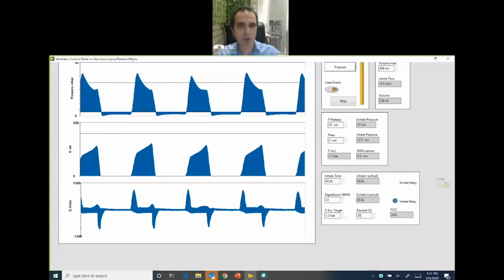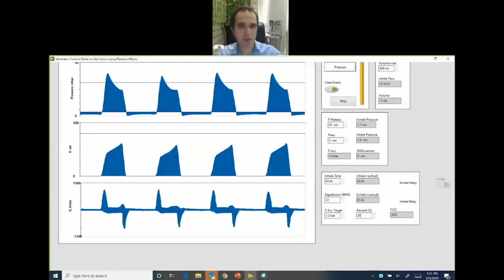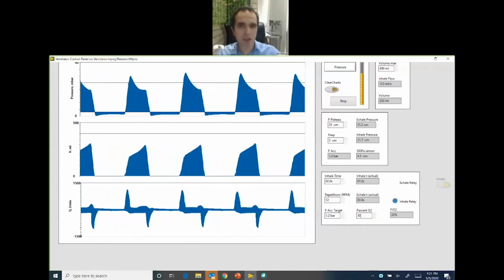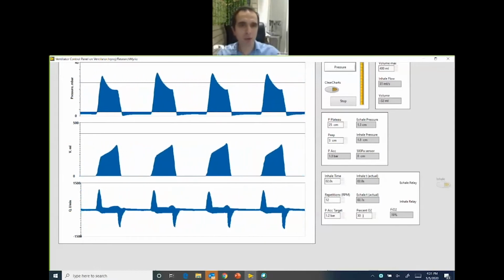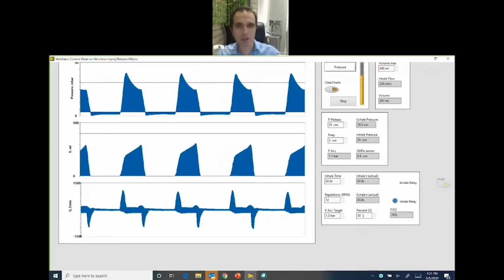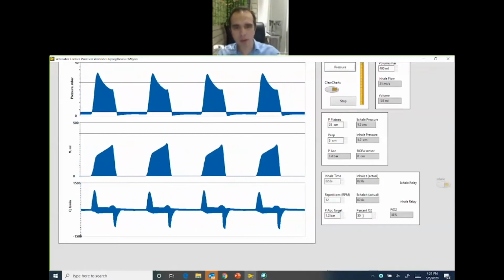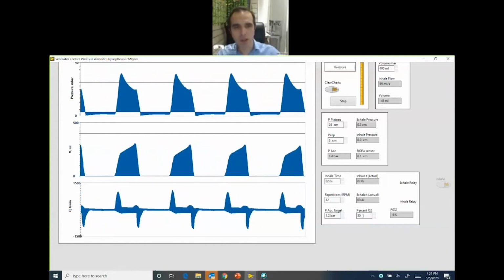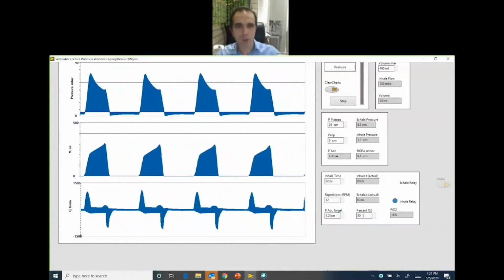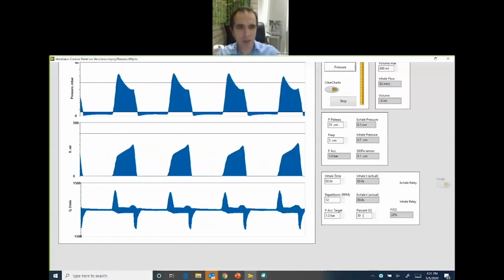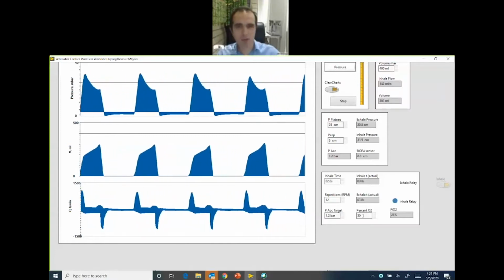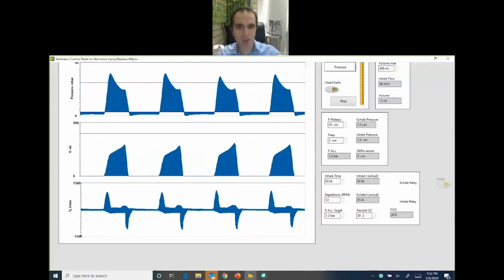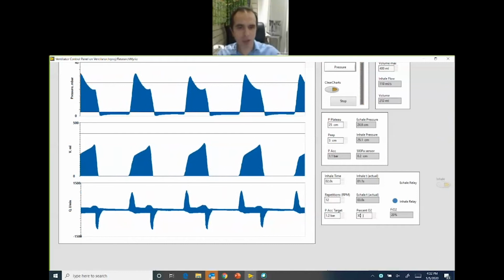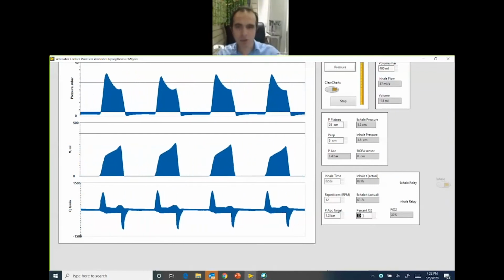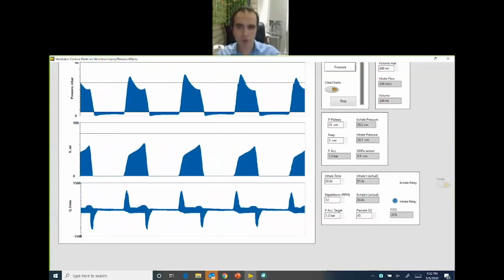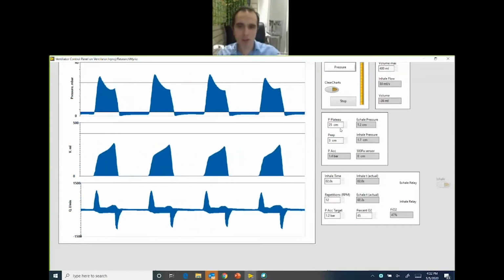We also need to fabricate a part for an important component in the system, which is the flow regulating valve. This is very important because, as Paul was saying, we do not need just to control the amount of pressure that's going to the lungs of the patient. Once the pressure is accumulated inside the accumulator through these two solenoids, we have to control the value of the flow that's going to the patient through this outlet over here. This is the Venturi that will measure the flow, and we control the flow using this servo motor that you see over here. So the servo motor is attached to a simple ball valve.